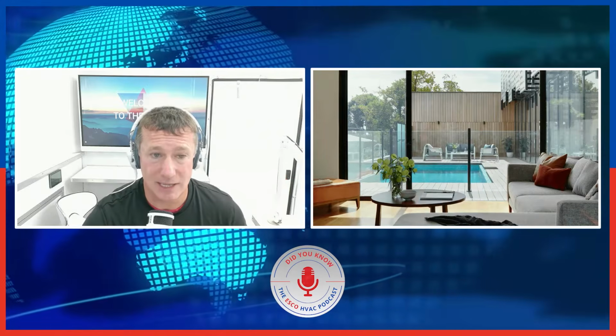Yeah, absolutely. When I was doing commercial refrigeration, we also took care of all of the HVAC for the buildings as well. So you think about some of your larger grocery stores, right? You never put gauges on a unit unless your subcooling was off, right? We'd walk around. What's the ambient temperature? What's the discharge temperature? What's the liquid line temperature? Move on to the next one, right? These are all package units. If they got brand new clean filters after we clean the condensers, these things should be running in that ballpark, right? So that was what we did with every unit. If it was off, then we could get our gauges out and go determine, all right, what's happening on this thing. But we can go further than the subcooling.